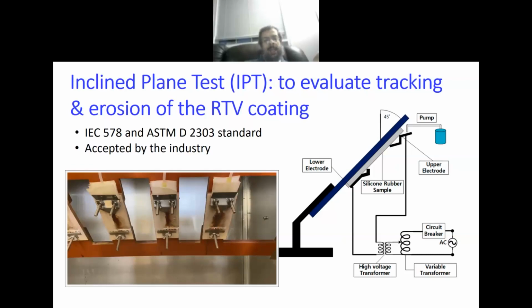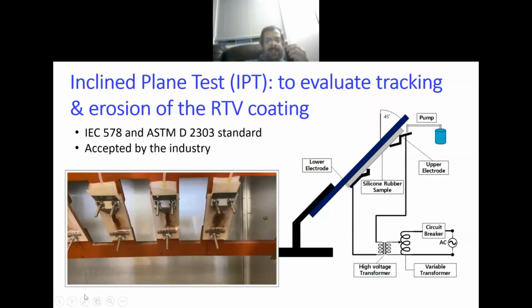So basically, what is this test? You have the samples. These white materials are the samples, and here is a sample of the silicone rubber. We have it at 45 degrees. Then we use peristaltic pumps to gradually pollute or wet the surface with a conductive material. You can see the pumps from the top of the samples, and these are some papers. They are wetted so that you have a smooth flow of the water, not a pulsating flow. Then here you have a high voltage and this is a ground end. So now you have a high voltage, a ground, and an electrolyte, and you will start to have arcing.